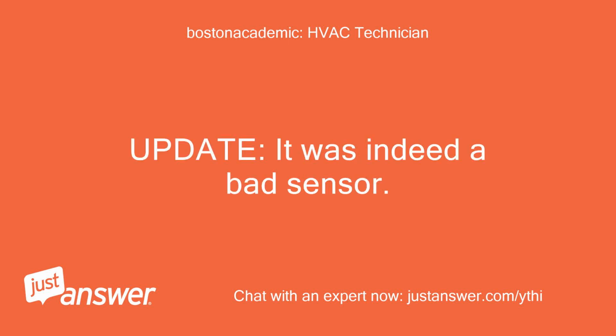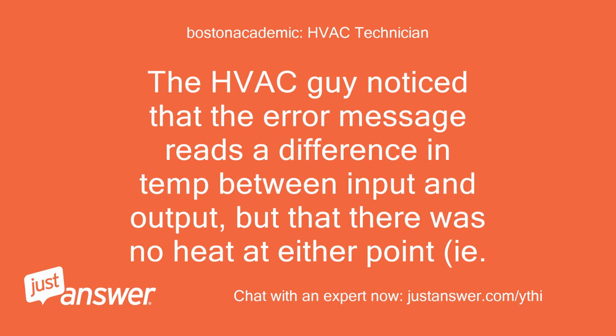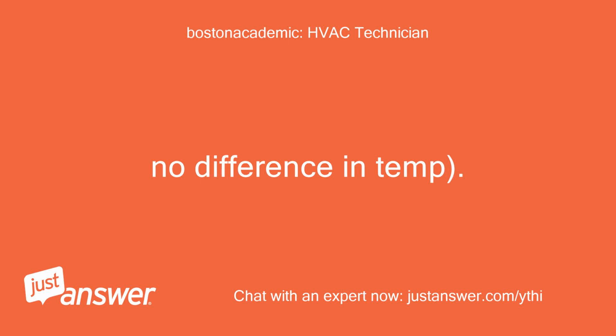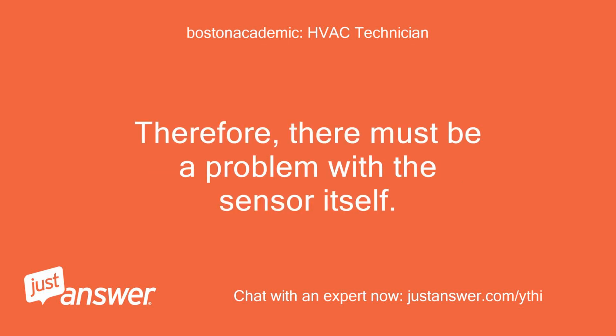Update: it was indeed a bad sensor. The HVAC guy noticed that the error message reads a difference in temperature between input and output, but there was no heat at either point, and no difference in temperature. Therefore, there must be a problem with the sensor itself.